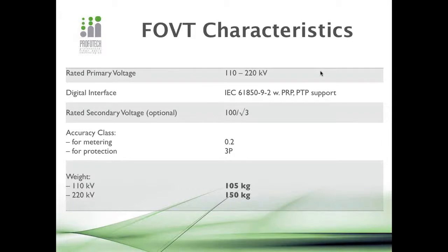The characteristics of this device: we basically have 110 and 220 kilovolts. Well, if we speak about the rated voltages in India, as far as I know, you must have maybe 133, and it's absolutely acceptable. It has a digital interface with IEC 61850-9-2, just as the previously mentioned current transformers. It also has an optional analog interface, which is 100 volts divided by square root of 3. Its accuracy class for metering is 0.2 and for protection is 3P.